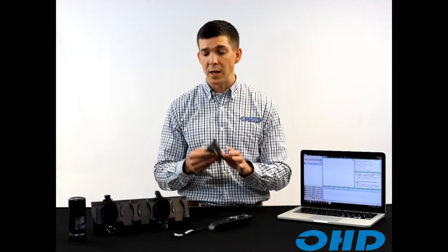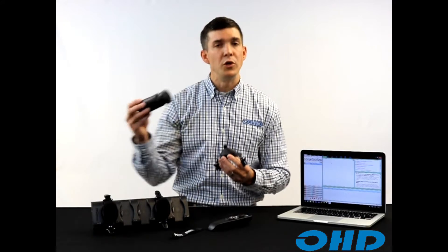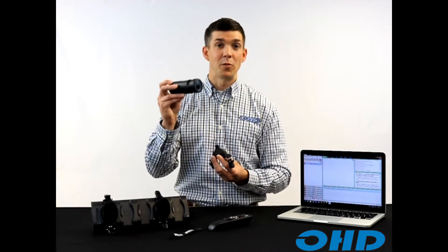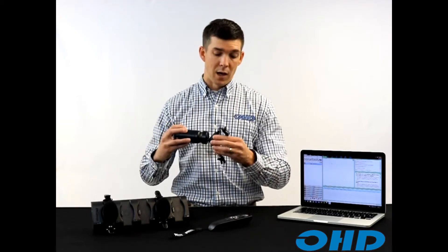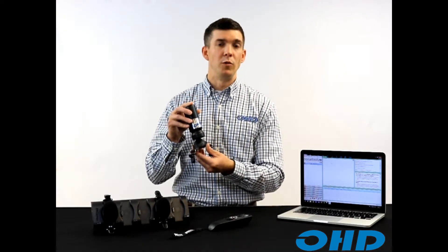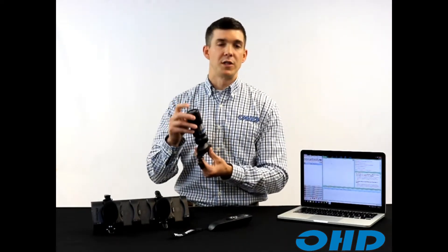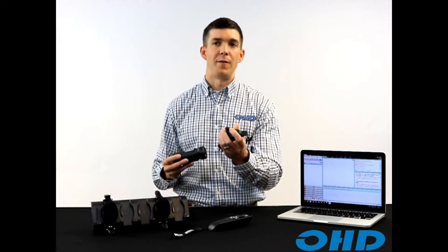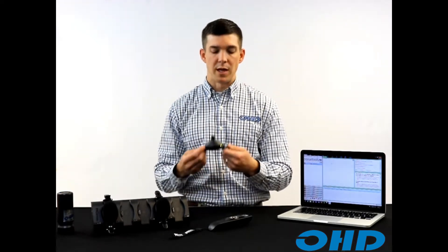Another important new feature compared to the old Dose Badge is calibration. Previously you had to have a reader to do some of the downloads and calibrations. Now we've transitioned to a simple sound level meter calibrator that operates in the same way you would with your sound level meter — you put the decibel measurement through and calibrate your dosimeter. Very easy measurement process.